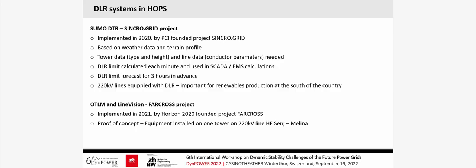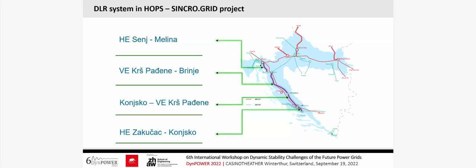This gave us a chance to compare the results and check if the software-based solution is as good as directly measuring DTR or temperature on the line. We equipped those 4 lines with the DTR solution because most of the production from wind power plants is in the south, while most of the consumption is in the north. That's why those 4 lines were important as a corridor for power evacuation from the south.